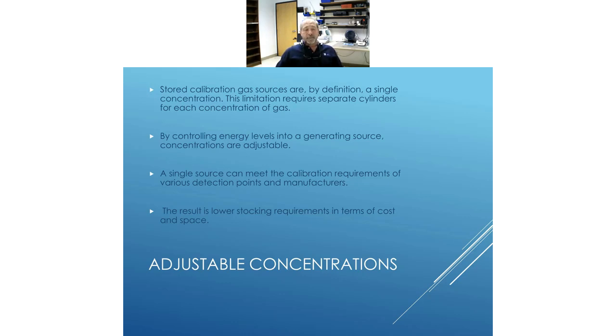So if you've got several different types or manufacturers' sensors, you might have to have several different cylinders. As I mentioned before, with these gas generators that we produce, you can just go through the display of the unit, set it at 1 ppm, calibrate all your 1 ppm sensors, then change it to 5 ppm, calibrate those. So a single source can make a lot of gas and can make it at varying concentrations, which for the end user allows for less storage. The cylinders are date stamped, and at a certain point they just expire, and you just have to throw them away as well. So if you haven't used them, you lose them.